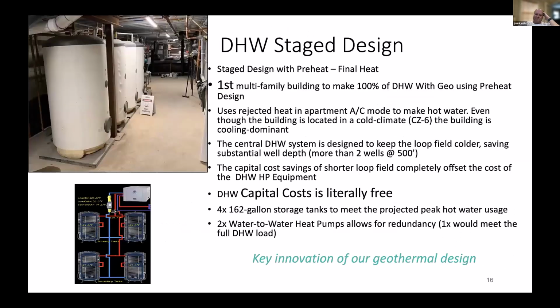water-to-water heat pumps. For the water usage, we use a stage design. That means we preheat it to expose the first heat pump to colder temperatures, which significantly increases their efficiency. And then a second set of tanks is doing the final conditioning to bring it up to 125, 130 degrees. We store about 640 gallons for that building here.